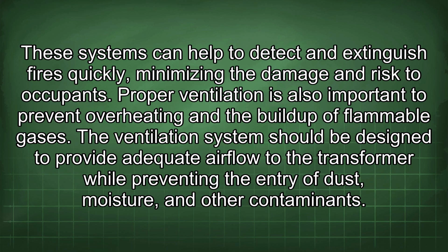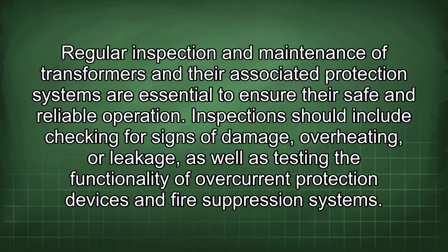These systems can help to detect and extinguish fires quickly, minimizing the damage and risk to occupants. Proper ventilation is also important to prevent overheating and the buildup of flammable gases. The ventilation system should be designed to provide adequate airflow to the transformer while preventing the entry of dust, moisture, and other contaminants.